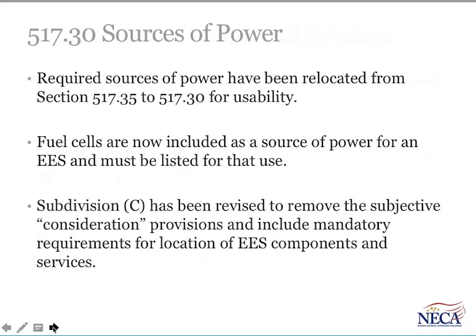517.30 is not new. It covers required sources of power. It's been relocated from 517.35 to 517.30 to provide a more logical layout, really. That's what's going on here. But there is a change in there to incorporate fuel cells. Fuel cells are now included as a source for an essential electrical system. If a fuel cell is used as a source, it must be listed for that use.